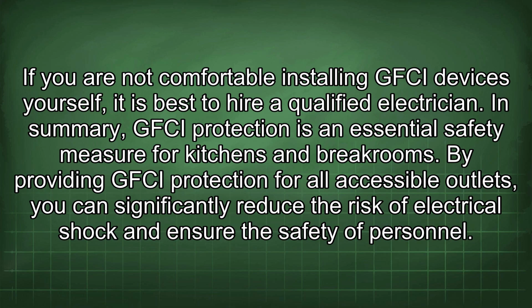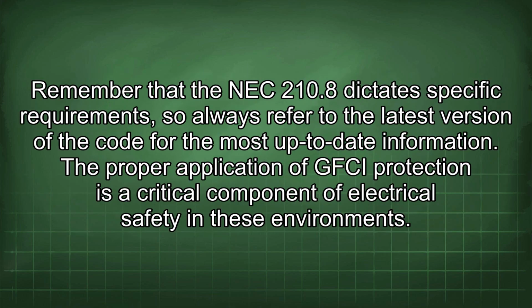In summary, GFCI protection is an essential safety measure for kitchens and breakrooms. By providing GFCI protection for all accessible outlets, you can significantly reduce the risk of electrical shock and ensure the safety of personnel. Remember that the NEC 210.8 dictates specific requirements, so always refer to the latest version of the code for the most up-to-date information. The proper application of GFCI protection is a critical component of electrical safety in these environments.